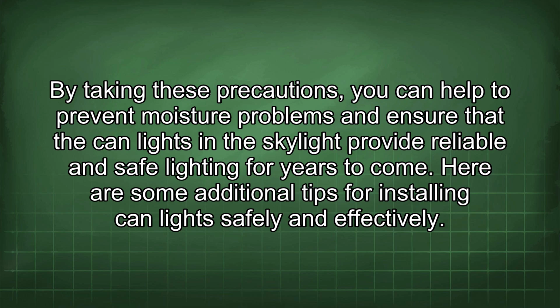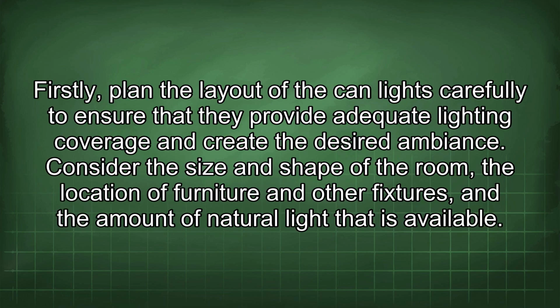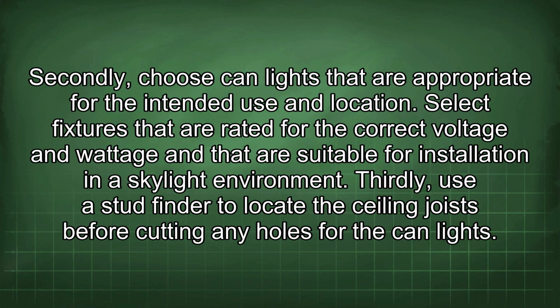Here are some additional tips for installing can lights safely and effectively. Firstly, plan the layout of the can lights carefully to ensure that they provide adequate lighting coverage and create the desired ambience. Consider the size and shape of the room, the location of furniture and other fixtures, and the amount of natural light that is available. Secondly, choose can lights that are appropriate for the intended use and location. Select fixtures that are rated for the correct voltage and wattage and that are suitable for installation in a skylight environment.